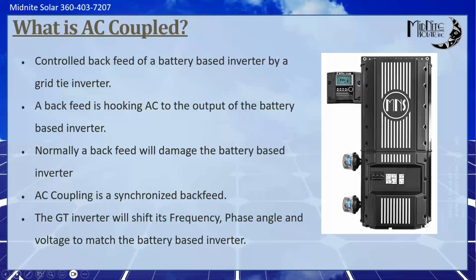You will damage that inverter. That's been hammered into you for years and years. Well, now we're going to tell you to go ahead and connect that source to it, because it's a grid tie inverter, and the grid tie inverter will actually regulate and synchronize. So that's how we get around this. That's how it's okay. I've got a video out there that I'll try to remember to put up on Facebook when we're done.